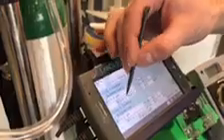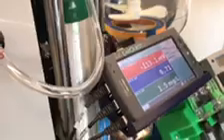Furthermore, on the other side we have activate line 3, or our acid pump, if the pH is greater than or equal to 7.2. Notice we have 6.8 to 7.2. That is our dead band, so we're not fighting the high alkaline to the high acidic. So now we'll hit OK. And one other thing to mention here, we have our alkaline pump coming on right now because our pH is reading 6.7. As you can remember, it said turn on the alkaline pump if it falls below 6.8.